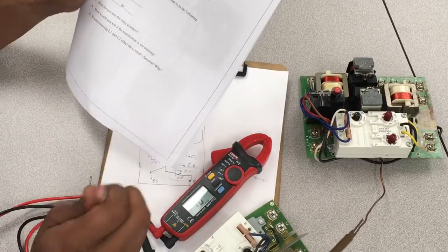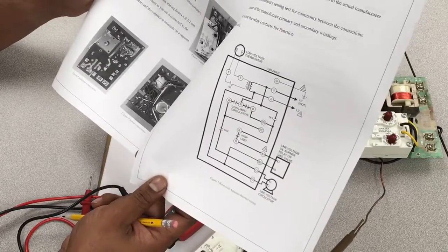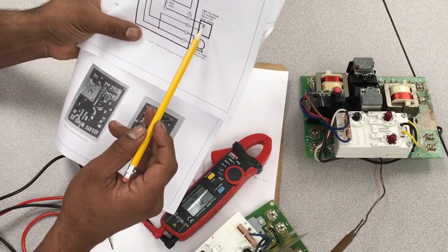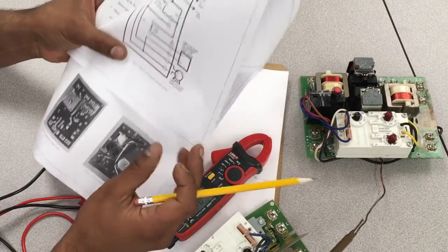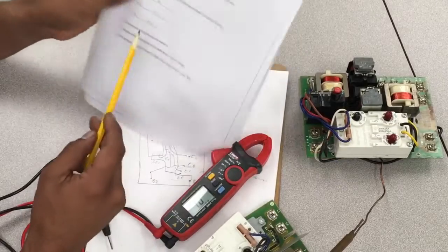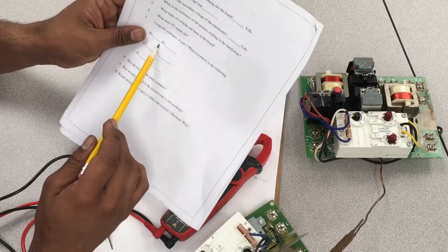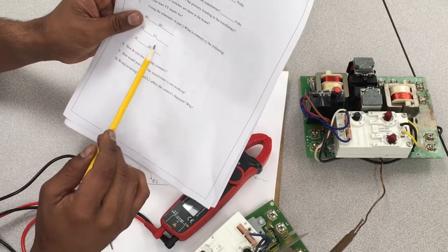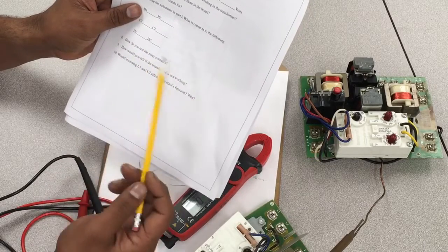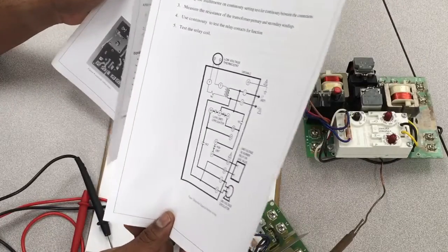Using the schematic in part 2, connect to the following. If you look at these connections here, you can see that B1 and B2 connect to the burner control, and C1 and C2 connect to the circulator. ZR and ZC are connections to an additional zone. You can notice that one of them is neutral, one of them is hot, and one of them is neutral. So B2 is neutral, C2 is neutral, and this is zone neutral. And probably the ZC stands for Z common, and ZR is probably Z red, or the line voltage coming to it.